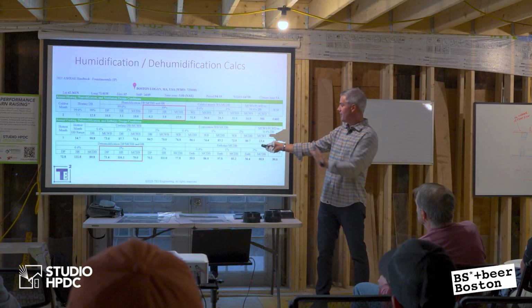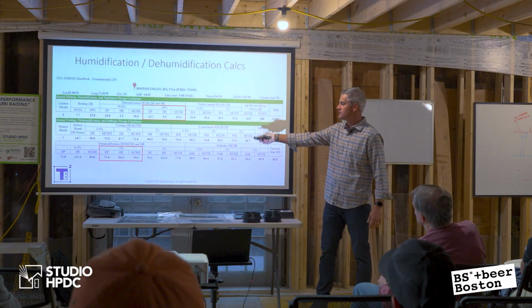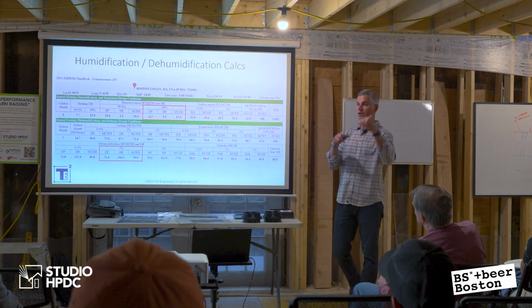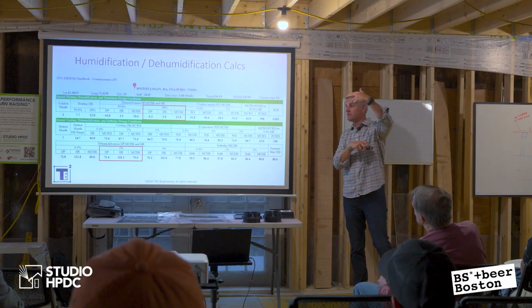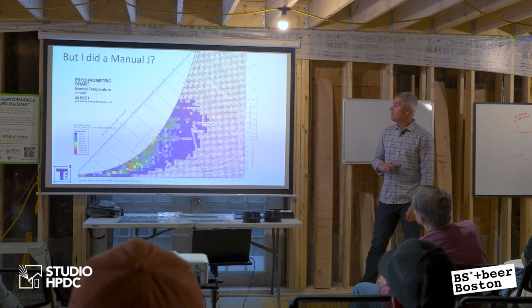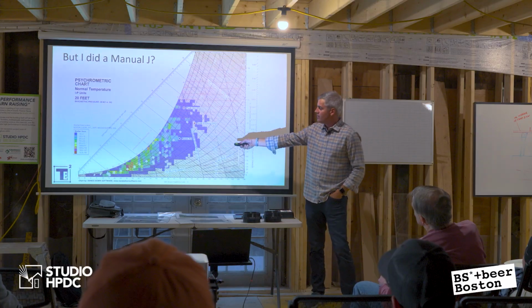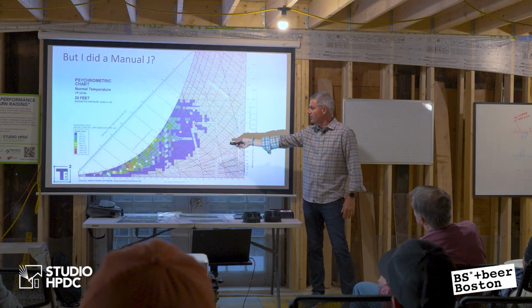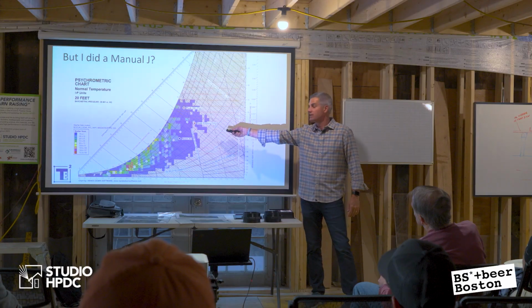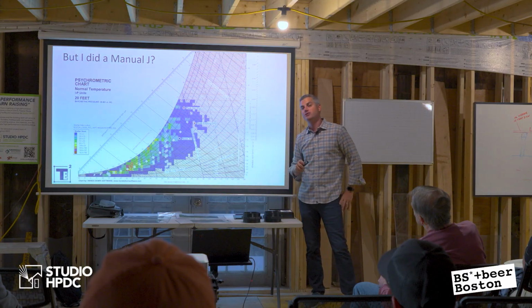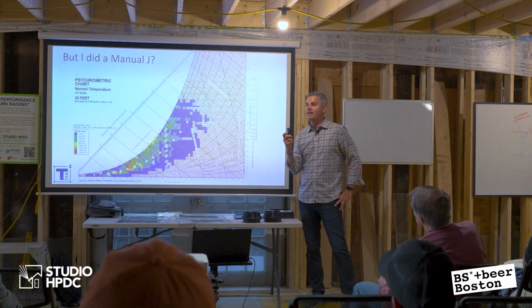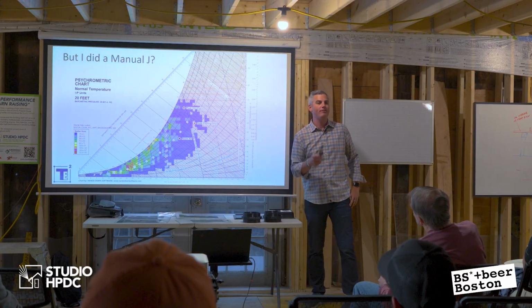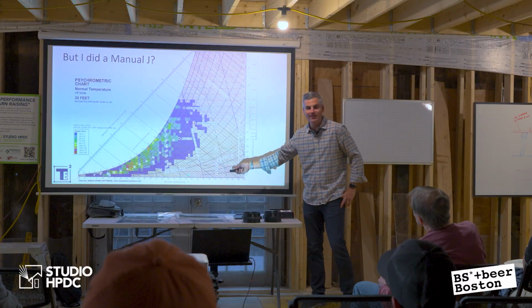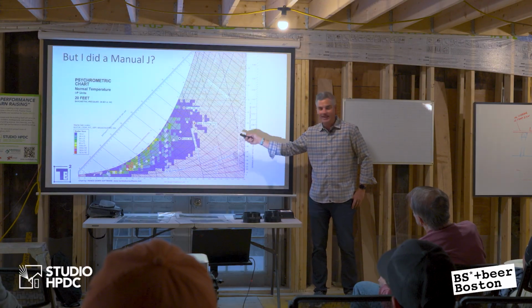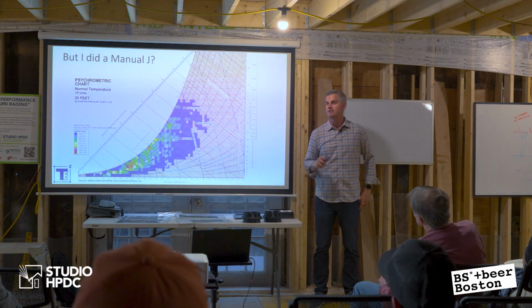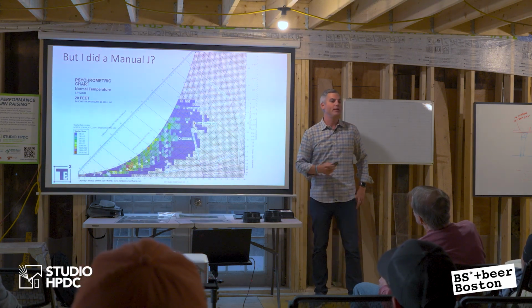Humidification and dehumidification. Again, we're coming back to that chart. We can figure out what our humidification load is and what our dehumidification load is. Both, if you think of that psych chart, in the worst case winter and the worst case summer conditions for moisture. The reason I bring this up is because on the cooling side, here's our room air. Again, it's 75 degrees, 50% RH. Here's our peak cooling. That's our Manual J, 1% condition. But guess what? That's our peak dehumidification. A lot of people don't understand that actually the most moisture that we have in Boston outdoors happens at around 80 degrees outside, not 90, not 88 degrees. So people think, oh, it's 95 degrees out and 90% relative humidity.